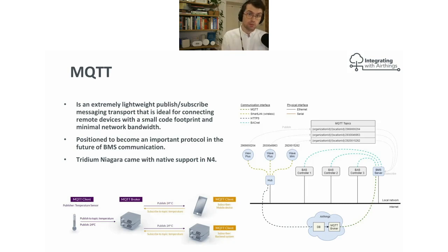There's no security implication within your building. To get that data into your building automation system, we host an MQTT broker, and the BMS server within the building could then subscribe to specific topics for all of these devices. You could then run MQTT locally within the building, or if you have a traditional protocol like, for example, BACnet or Modbus communicating to all the actuators within your building, your heating, cooling coils, your fans, or other things you want to initiate based on air quality data, they can then communicate within the building.